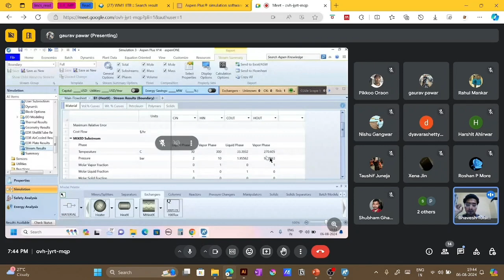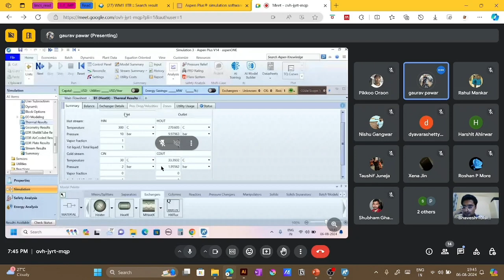Now can you go to the thermal result part and the exchanger details now. Here you can see the required exchanger area is 0.467 meter square, while the design that we have provided, the exchanger area is 50.58. So that is very heavily over-designed, right?